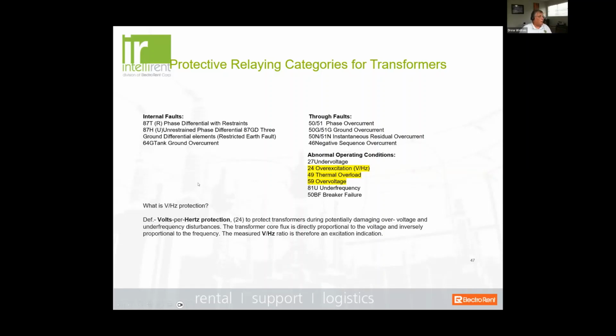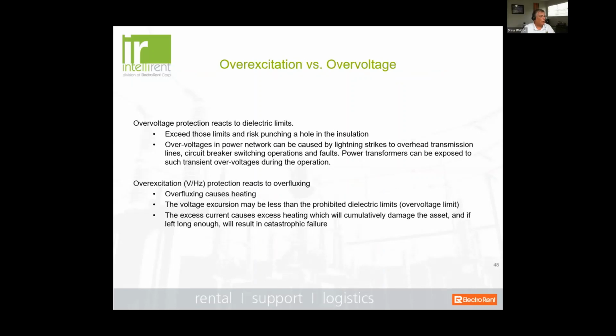So what is volts per hertz protection? Well, that's the condition that can potentially damage the transformer from having an overvoltage and under frequency simultaneously. So that's not just one or the other, but it's a combination of both and a ratio of voltage to frequency. In some terminology, it's called overexcitation.